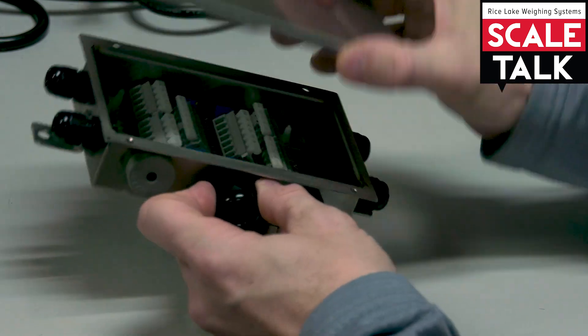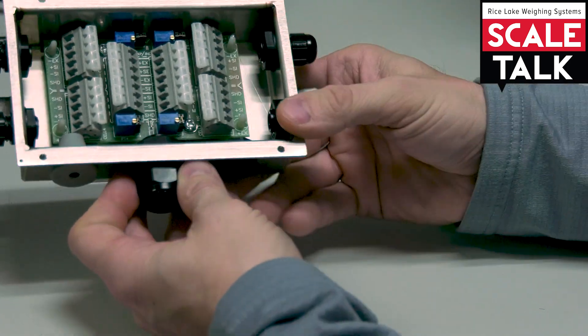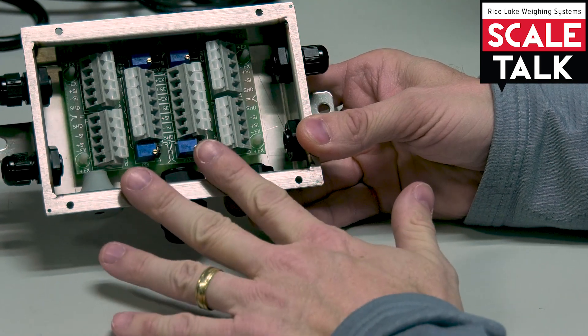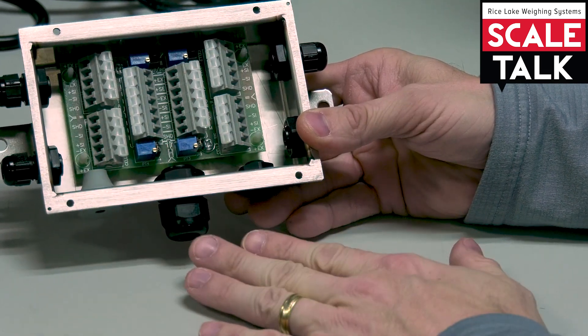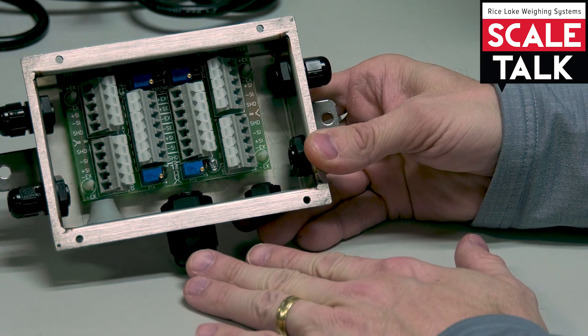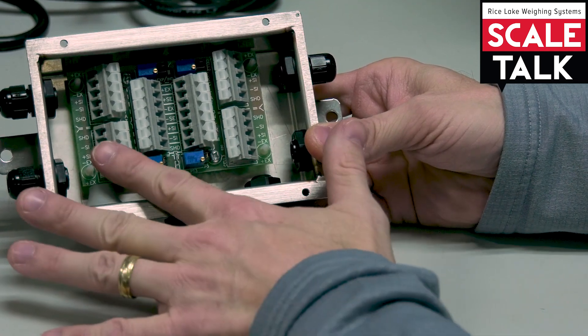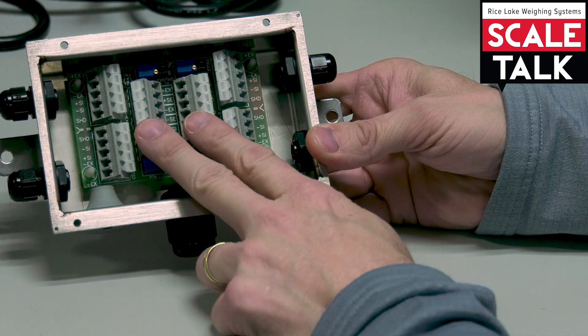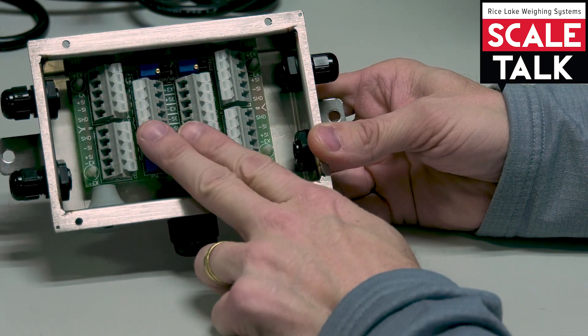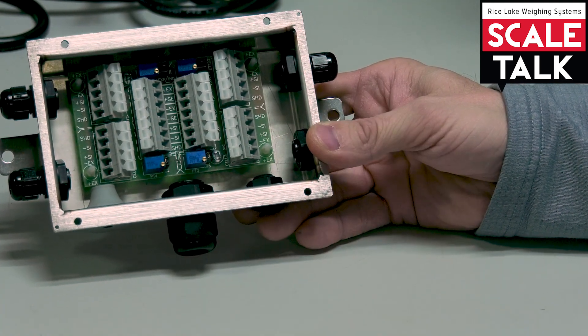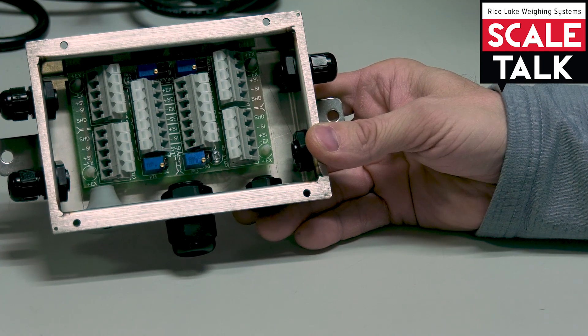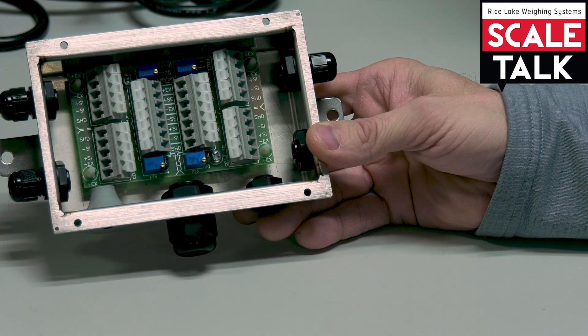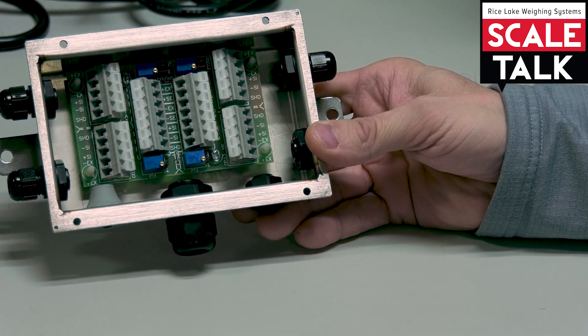And so in a J-Box, we have this capability. In this example here, this is a four-channel J-Box, so it allows me to bring up to four load cells in here. I've got four different channels, and then I've got two spots here in the middle. One of these is going to wire back to the indicator. We would call that our home run cable, and that's where the signal is going to come back to the indicator so it can be interpreted by the A to D and give us a weight.